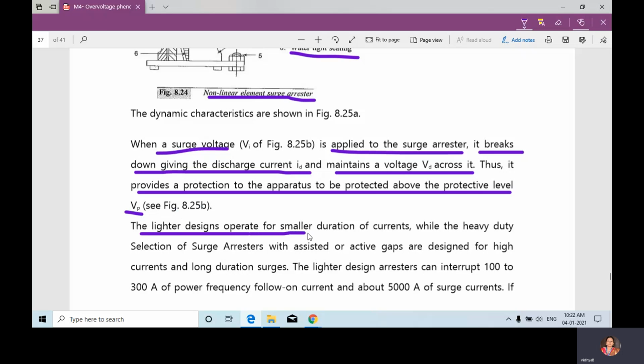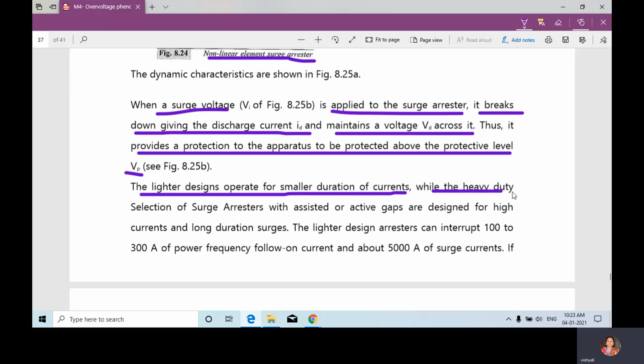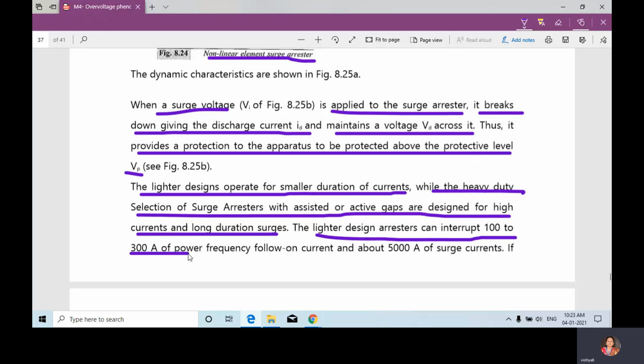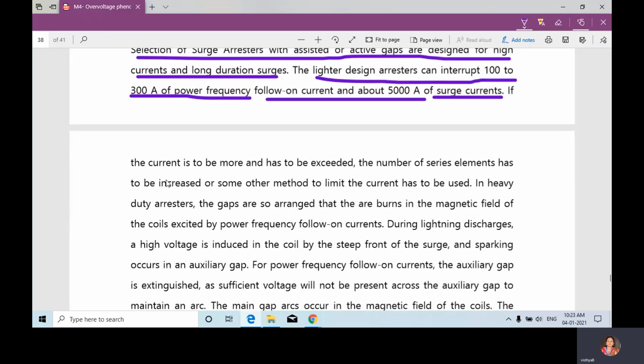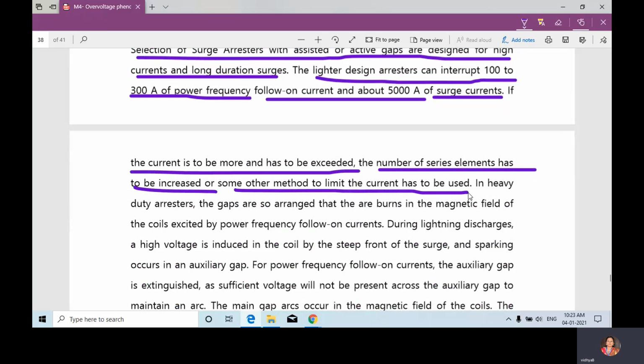The lighter designs operate for smaller durations of current, while the heavy duty selection of surge arrestor with assisted or active gaps are designed for high current and long duration surges. The lighter design arrestor can interrupt 100 to 300 amps of power frequency follow-on current and about 5000 amps of surge currents. If the current is to be more and has to be exceeded, the number of series elements has to be increased, or some other method to limit the current has to be used.